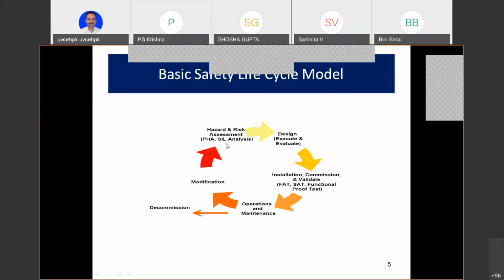That is nothing but it gives you an index of how the safety instrument system is performing. It's a statistical value. It will give you a number, SIL 1, SIL 2, SIL 3, SIL 4. SIL 4 is the gold plated. SIL 3, slightly lower order. SIL 2, slightly lower order. SIL 1, the lowest, in terms of reliability or performance points. SIL 4 is not talked about because to build a plant with SIL 4, people will lose every bit of money in that. That's not done except in atomic reactors and all that. No one goes to SIL 4. Up to SIL 3 is okay.